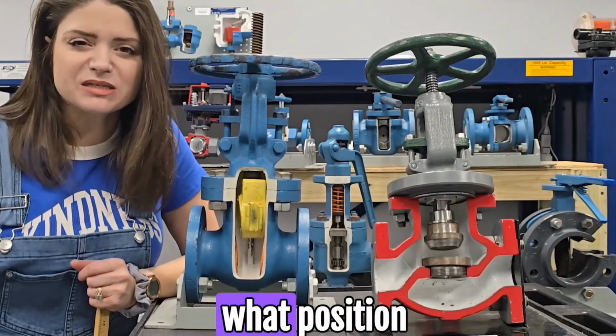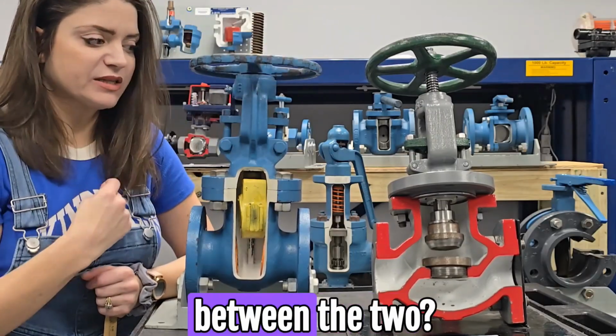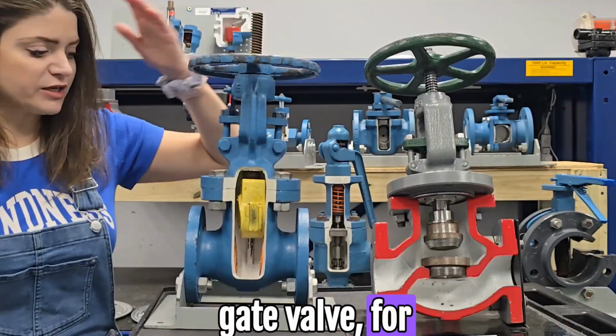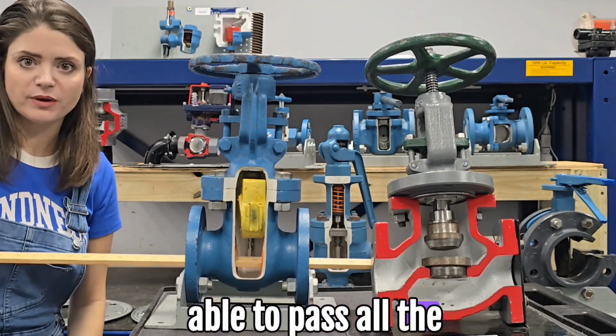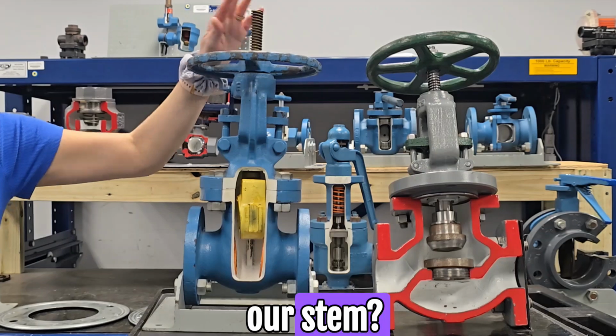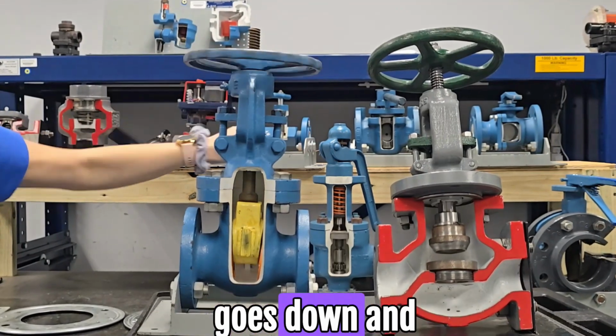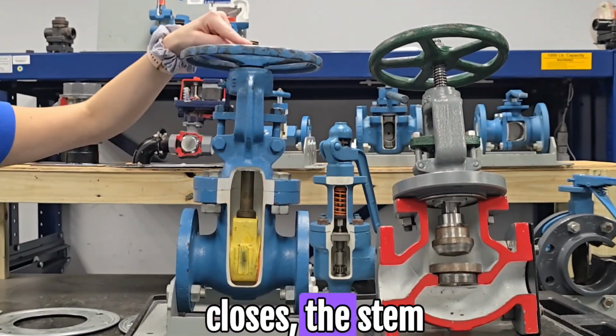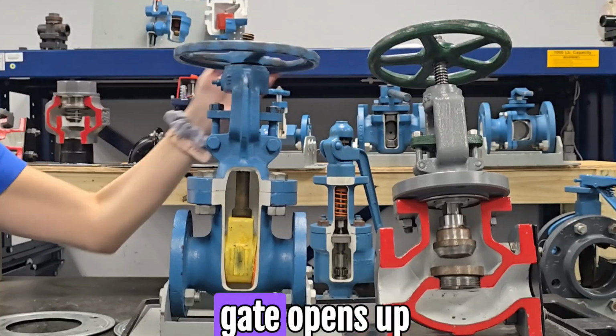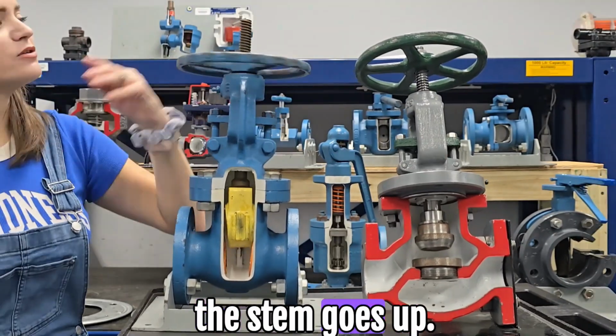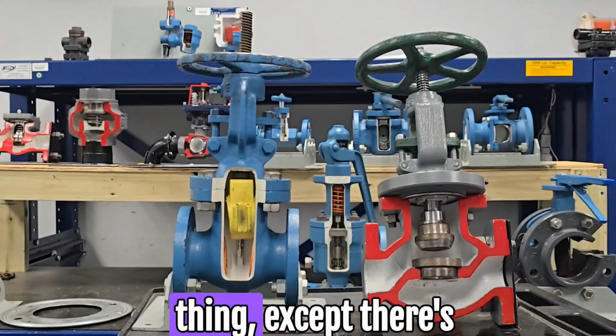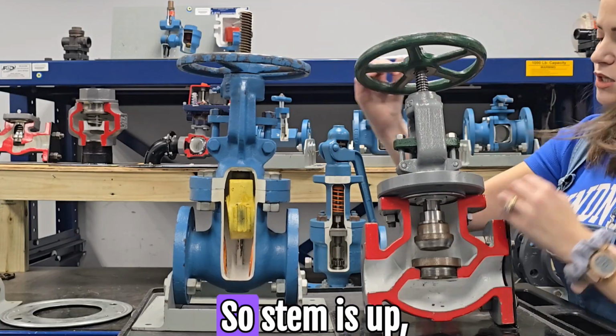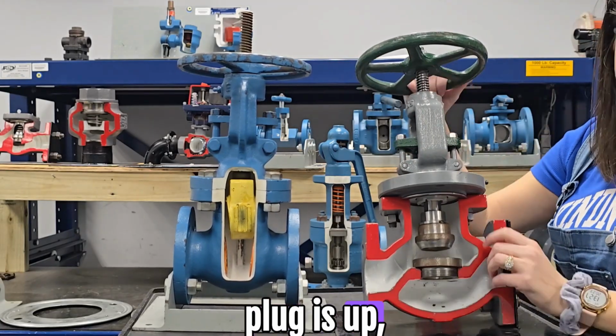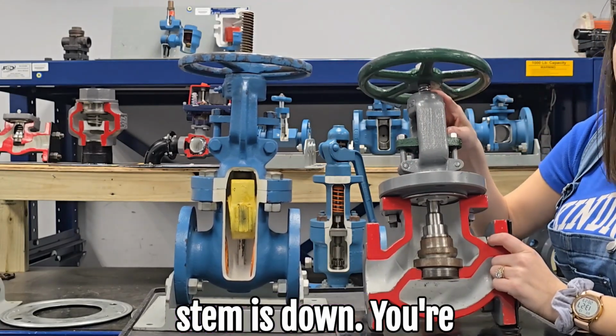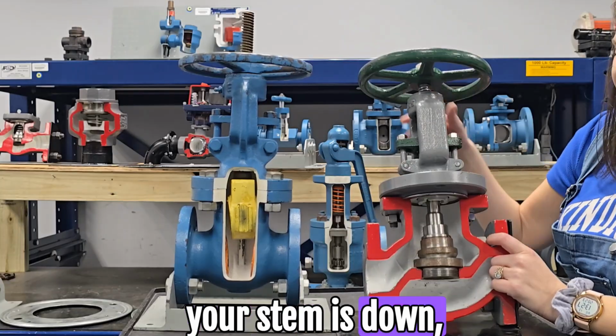So how can you tell what position they're in and tell the difference between the two? Let's look at our gate valve, for instance. Our gate is up, so our flow is able to pass all the way through, right? What else is up? Our stem. So notice as the gate goes down and closes, the stem goes down. As the gate opens up and lifts up, the stem goes up. Globe is the same thing, except there's a handle attached to the top. So stem is up, plug is up. Close it, stem is down. You're still going to have a thread or two, but your stem is down, it's closed.